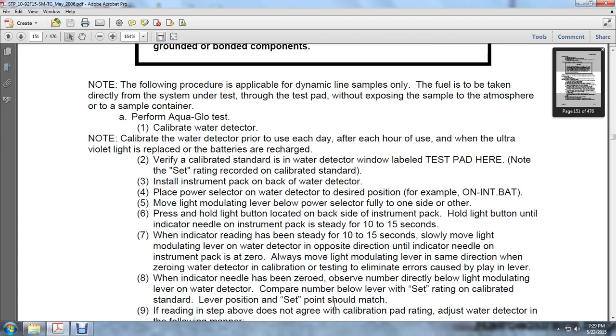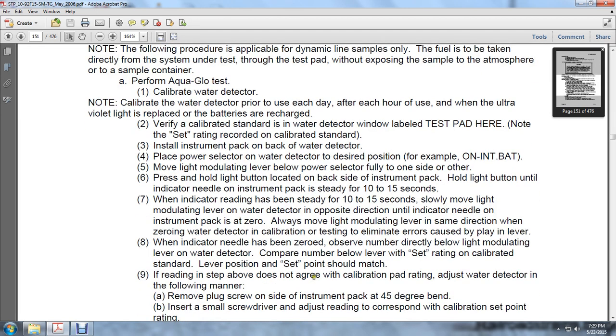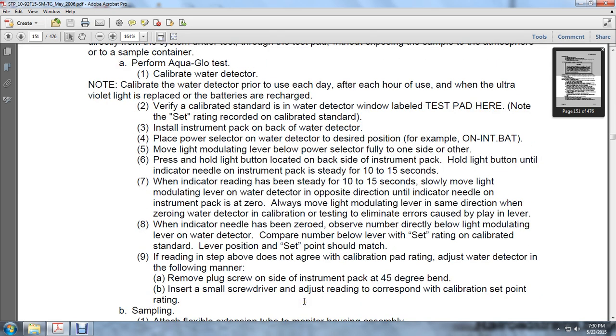If the reading does not agree with the calibration pad rating, adjust the water detector in the following manner. Remove the plug on the side of the instrument pack with the 45-degree bend. Insert a small screwdriver. Adjust the reading to correspond with the calibration set point rating. If the reading still does not agree with the calibration pad reading, repeat the adjustment: remove the screw plug on the side of the instrument pack and insert the small screwdriver, adjusting to the calibration set point rating.